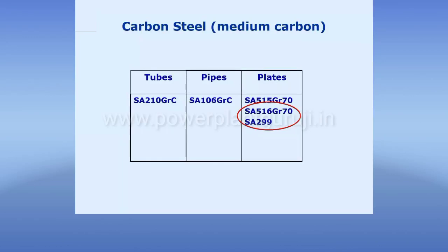The problem with carbon steel metallurgy is we can only use carbon steel where the temperature is less than 400 degrees centigrade, because the moment the temperature exceeds 370 degrees centigrade and nears 400 degrees centigrade, a particular problem starts in the component which is under pressure and temperature — that is called creep. Carbon steel does not have any significant strength against creep, so we need to add some alloying elements which can increase its strength against creep.